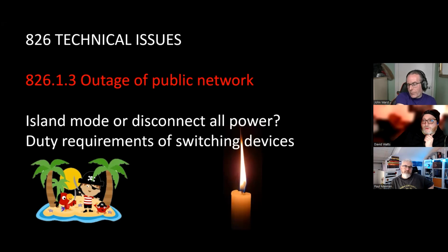Now, outage to public network. So in other words, if the grid connection goes away or there's some problem with that, you've got 2 choices. You can go into island mode and keep running, or you can just disconnect the whole lot, which is generally what happens at the moment. You've also got to consider the requirements of any switching devices. Are they actually up to the job of disconnecting and reconnecting the various types of loads you've got, and whether it's in island mode or connected modes? Just because you've got something that's suitable for connecting to the grid does not mean automatically it's suitable for connecting via your battery storage or any other types of system.